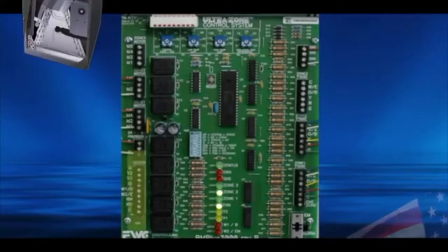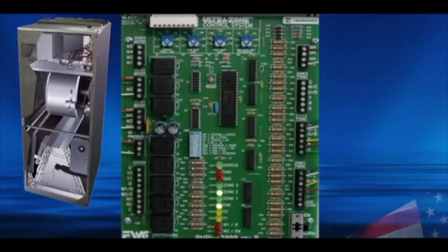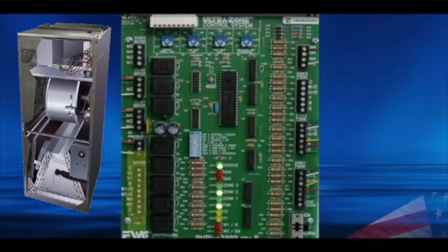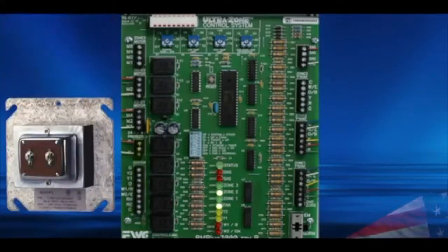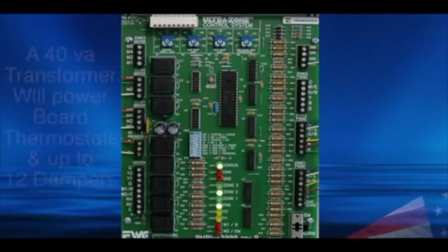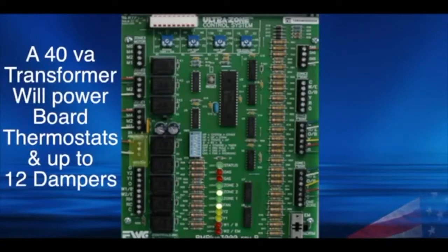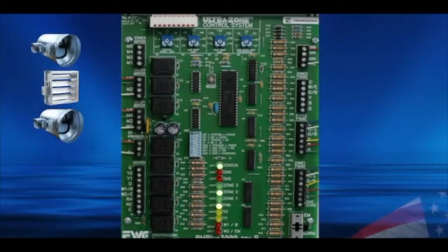or company needs. The system terminal block is where the equipment is connected. Wire the board just like you were wiring a thermostat. Wherever the thermostat connects to the system is where you connect the board. 24 volt is where the independent power of the zoning system is connected. Please use an independent transformer for the zone board. A 40 VA transformer will power board, thermostats, and up to 12 dampers.